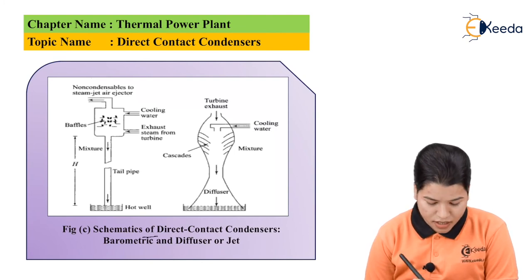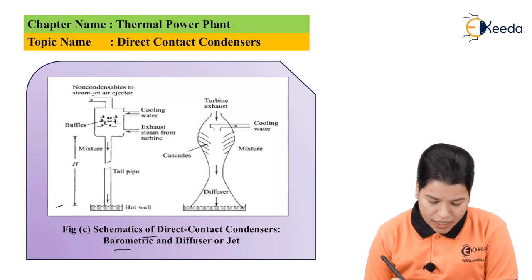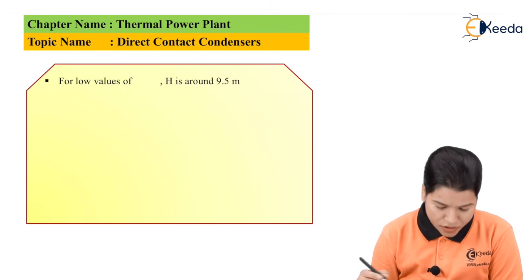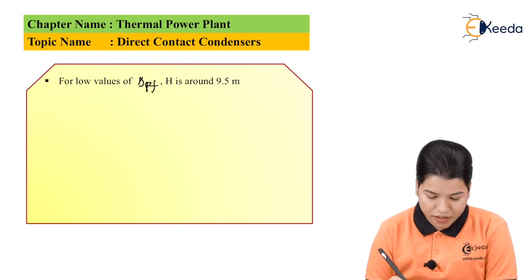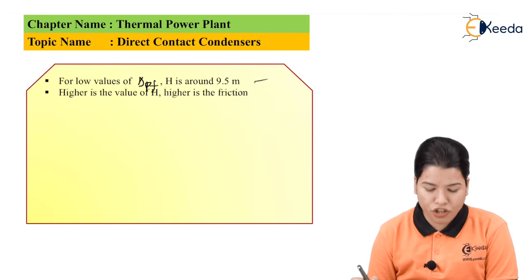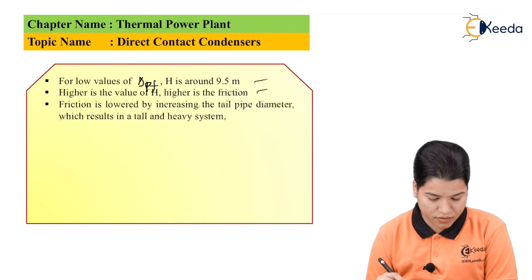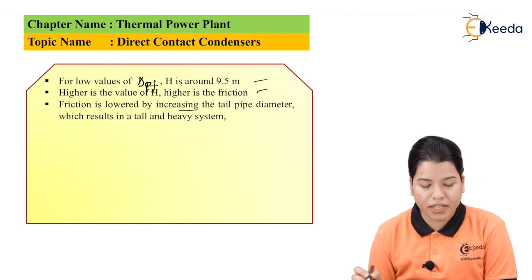For low values of delta_pf, the tail pipe height h is around 9.5 meters. A higher value of h corresponds to a higher value of friction. The friction can be lowered by increasing the tail pipe diameter, which results in a tall and heavy system.